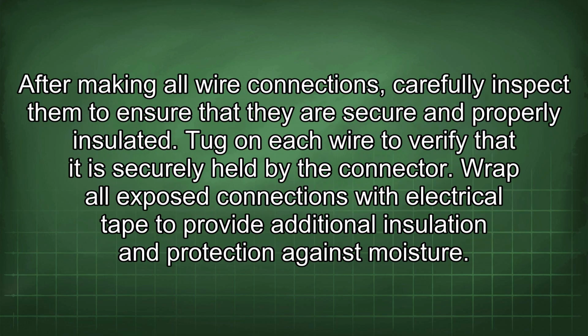After making all wire connections, carefully inspect them to ensure that they are secure and properly insulated. Tug on each wire to verify that it is securely held by the connector. Wrap all exposed connections with electrical tape to provide additional insulation and protection against moisture.